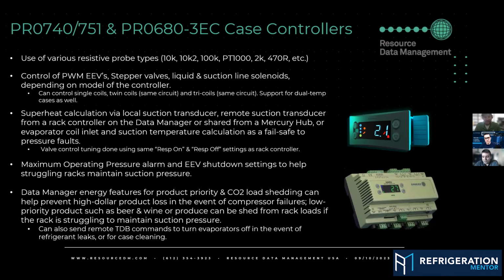But our case controllers, we have single, twin, and tri-coil case controllers. So our single and twin is going to be like our 740, 751 Mercury and Intuitive line. Our 3-coil case controllers, the PR0680 3EC controller, that's seeing a lot of use these days for some of those 12-foot cases that have 3-4 foot evaporators. They're installing a lot of those controllers. Yeah. So technicians are going to be seeing a lot of those.